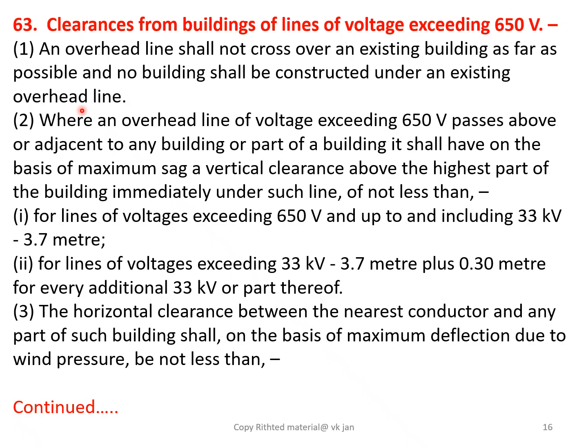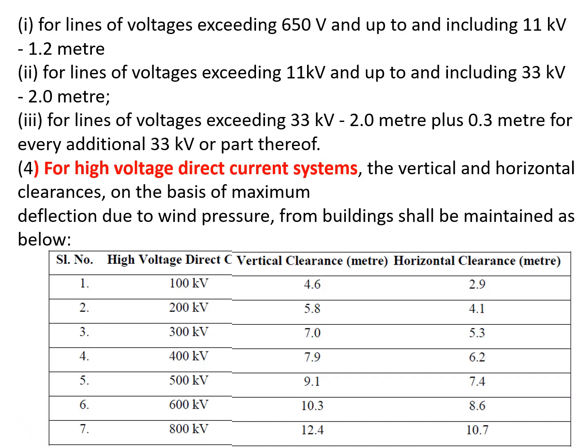Third, the horizontal clearance between the nearest conductor and any part of such building shall, on the basis of maximum deflection due to wind pressure, not be less than the following, given in the next slide. For lines of voltage exceeding 650 volt and up to 11 kV, 1.2 meter. Second, for lines of voltage exceeding 11 kV and up to and including 33 kV, 2 meter. For lines of voltage exceeding 33 kV, 2 meter plus 0.3 meter for every additional 33 kV or part thereof.